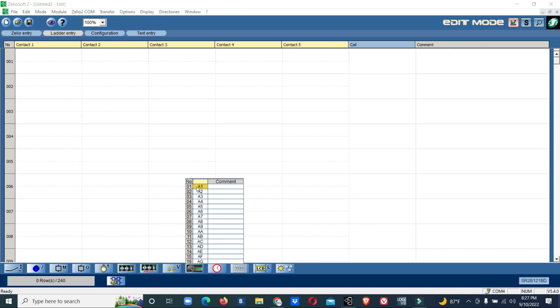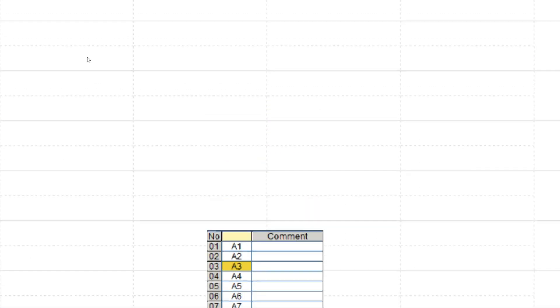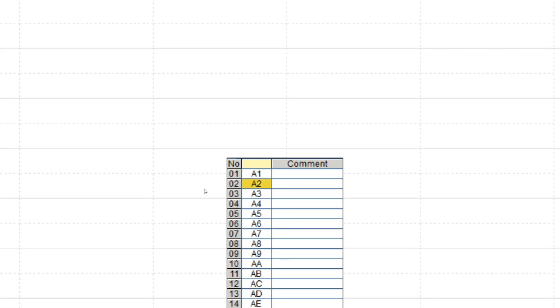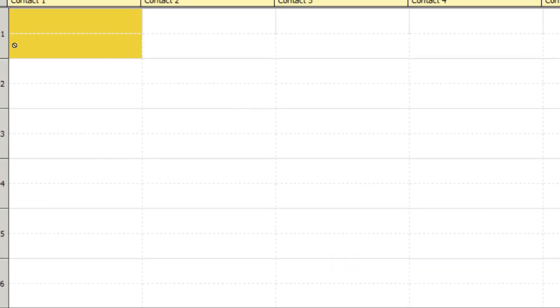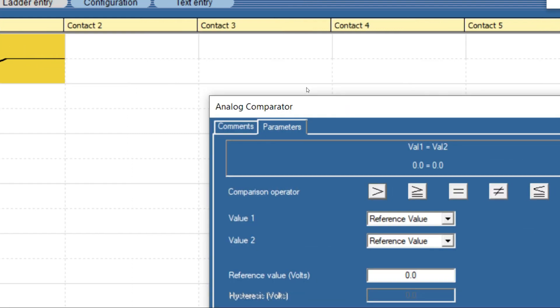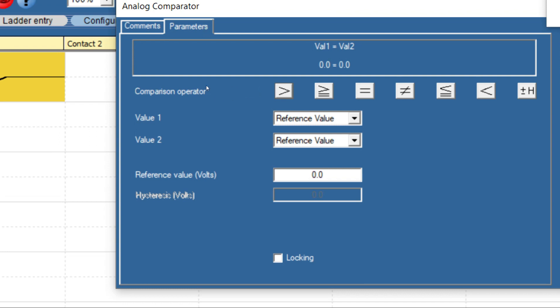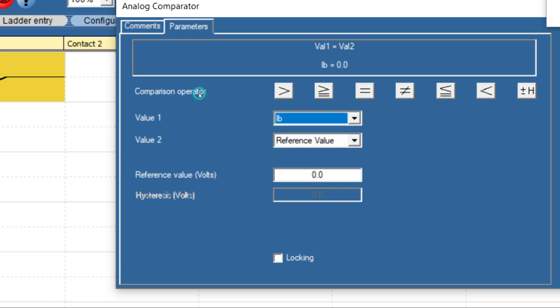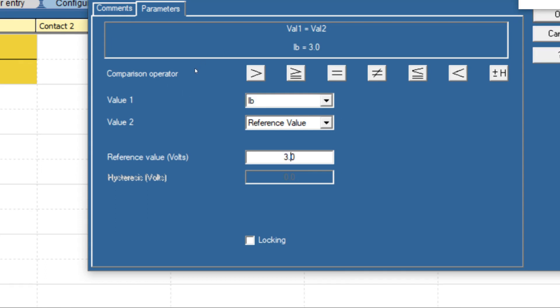We'll use an analog comparator and configure it. Our analog input is input IB. For the reference value, we can put direct voltage. Our input value is 0 to 10 volt with the reference of 0 to 10 bar as an example. That means we can configure till 9.9 volt in this Zelio. If it is 3 bar, then it should be 3 volt - below 3 volt means below 3 bar, so it should start.